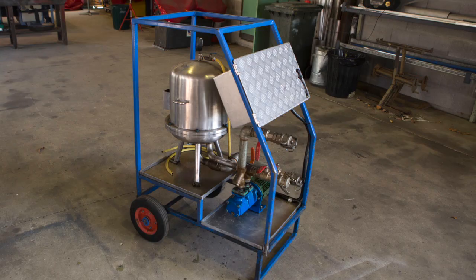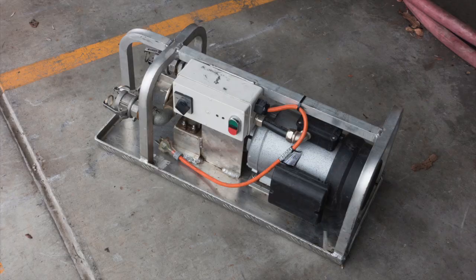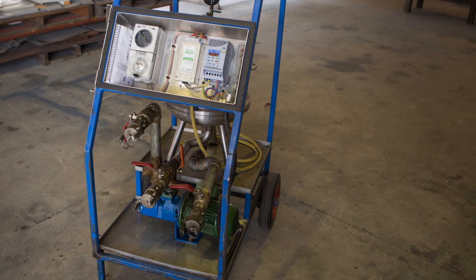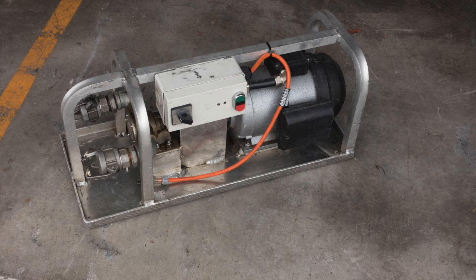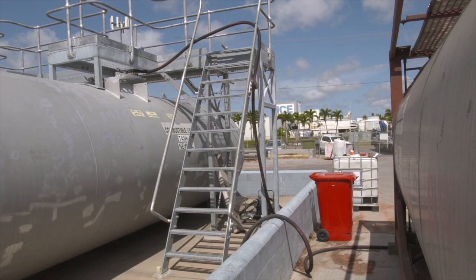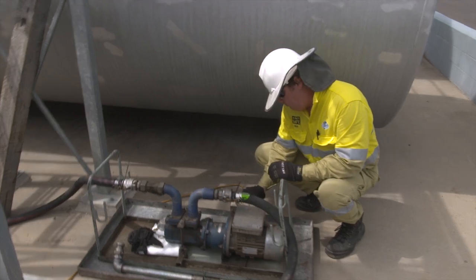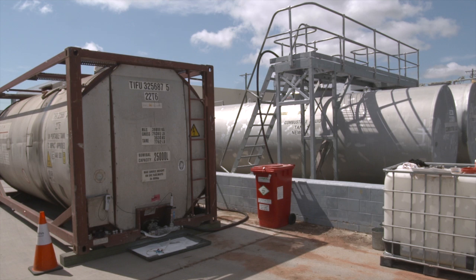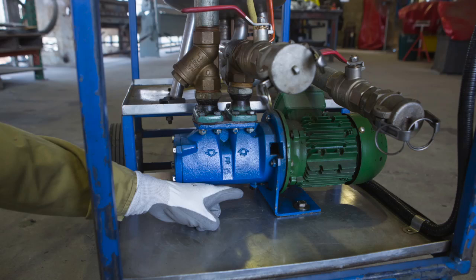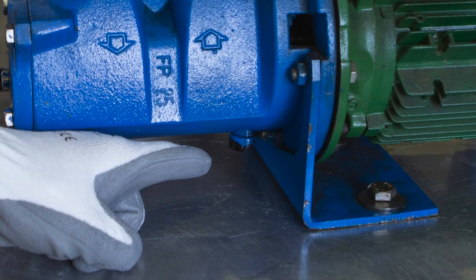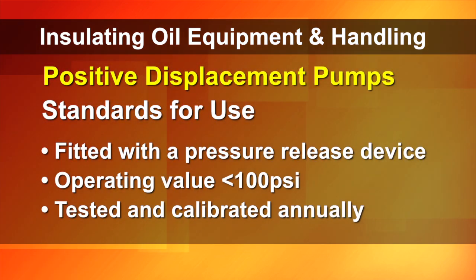We have two types of pumps used for the handling of oil within Ergon. Firstly, the positive displacement pump, commonly known as a gear pump. The second one is a rotodynamic pump, a centrifugal or a flexible impeller pump. In the event that somebody accidentally shuts off the valve on a positive displacement pump, the pressures can theoretically build up to very dangerous values. Part of this process, we are now requiring that pressure release devices be fitted to all positive displacement pumps, and the operating value of these must be less than 100 psi, and they must be tested and calibrated on a 12-monthly basis.